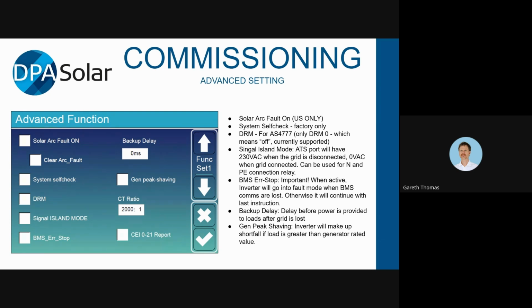Advanced function menu. Solar arc fault on. I don't know what that is. It just says for the US only. System self-check, again for the factory only, don't worry about that. DRM, this is an important one. This comes switched on as standard, I think. And so if you're not using it, if you're not in Queensland, you need to switch that off, otherwise the inverter won't turn on. The only DRM that it does, as far as I know at the moment, is DRM 0, which means when the grid requests the system to throttle the power, it will just throttle it all the way down to 0. But I think that's going to be changing in the future. And DRM is demand response. Demand response mode, yeah.